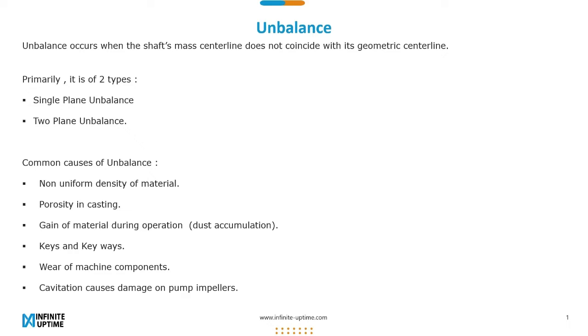The common causes of unbalance are non uniform density of material, porosity in casting, gain of material during operations, that is, dust accumulation, keys and keyways, wear of machine components, cavitation caused damage on pump impellers.